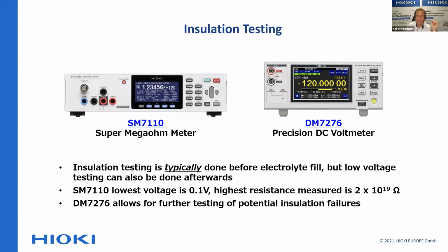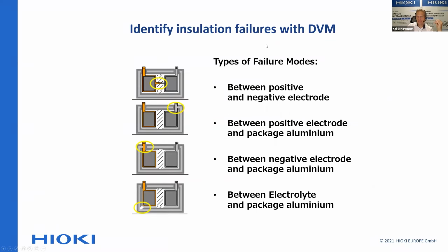Another thing in insulation testing is a precision DC voltmeter. You might wonder why on earth they're using a precision DC voltmeter, basically one part of a multimeter, for insulation testing. This is something that allows the digital voltmeter to measure a couple of scenarios simply by checking the actual voltage measured between certain contact points.